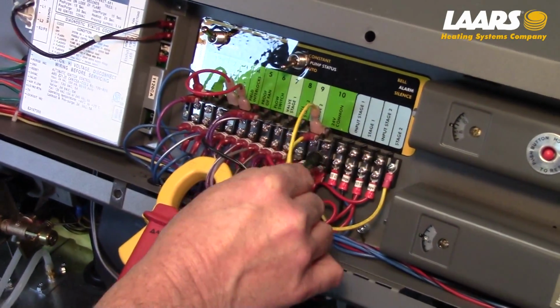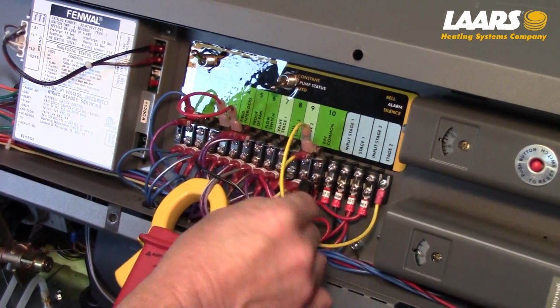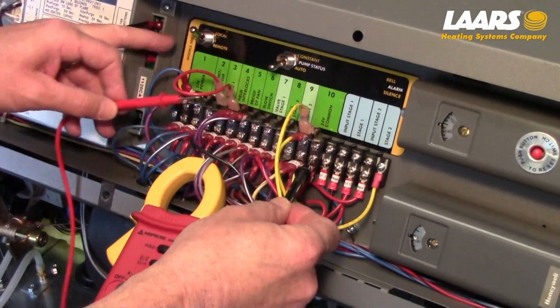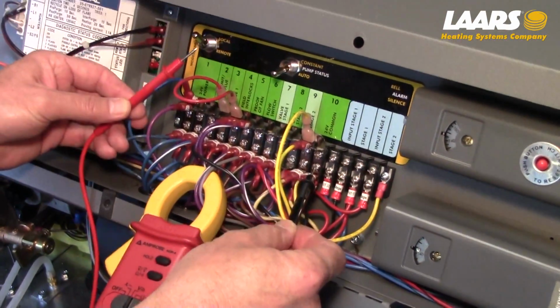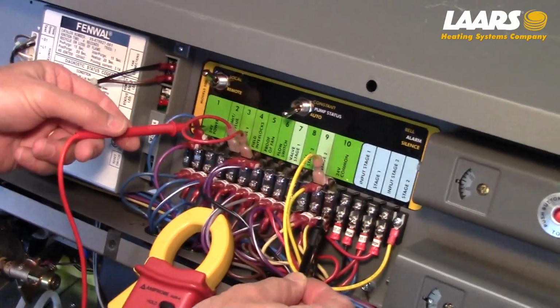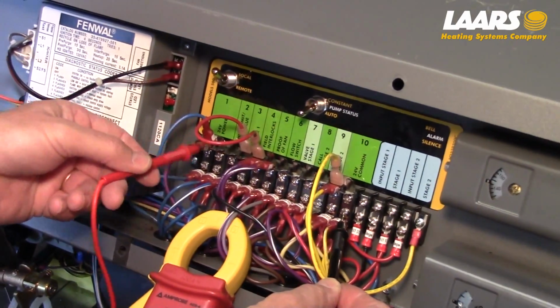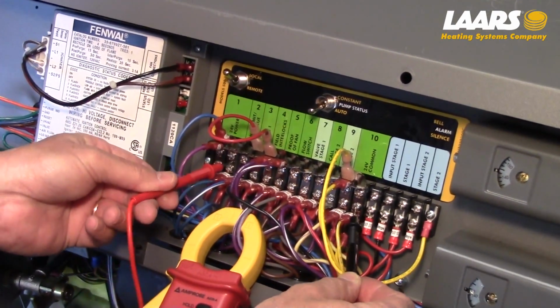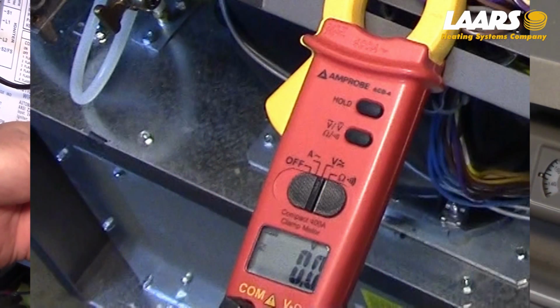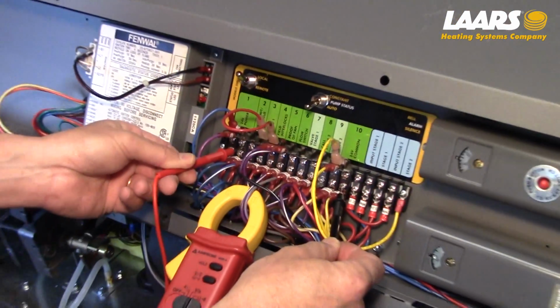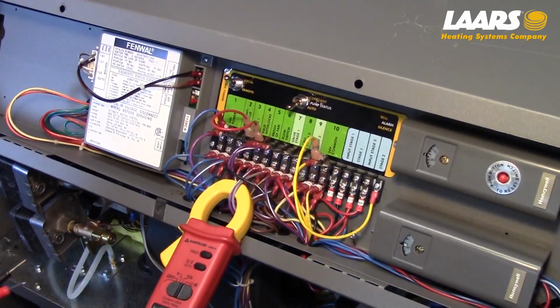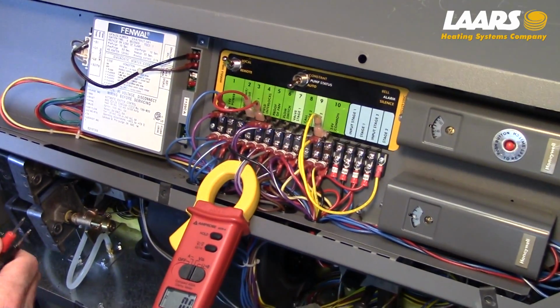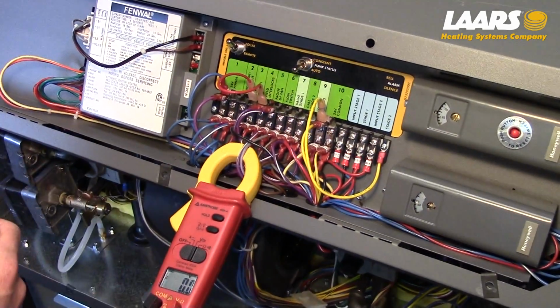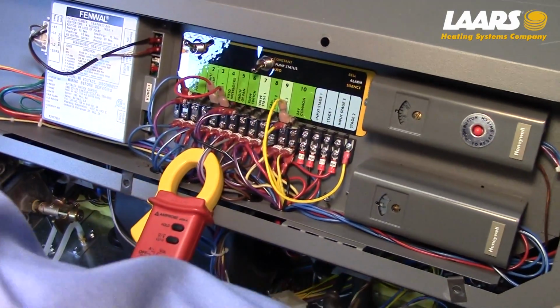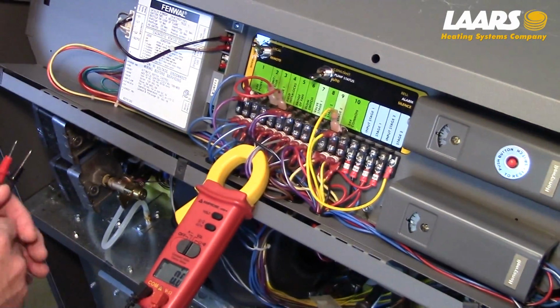Okay, now there are 2 sets of terminals for terminal 10. Any one of those. The next one over here is 24 volt power. I'm going to come over to my 24 volt power, which is 2 terminals here as well. And I'm going to place it here, and as you can see, I do not have voltage. Okay? So that's telling me that either I don't have line voltage or 120 volts coming in, or I have a blown fuse. So I'm going to double check my power.